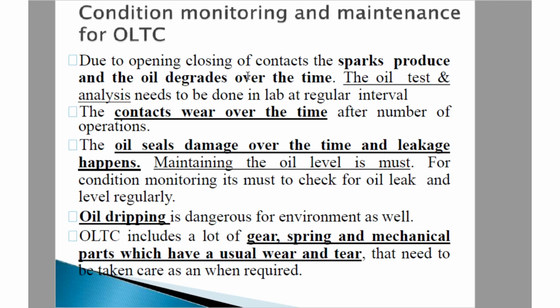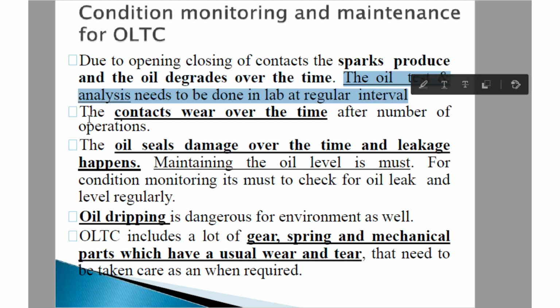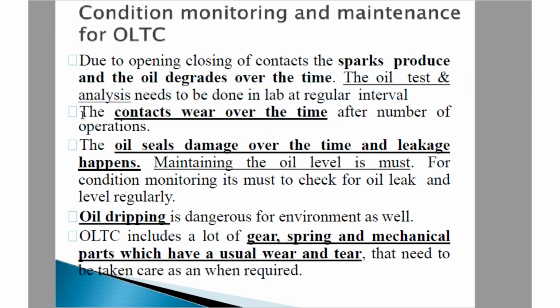We are interested in the condition monitoring and maintenance of OLTC. So this is the concept. Till now we have seen the concept of OLTC. Due to the opening and closing of the contacts, sparks are produced and the oil degrades over time. The oil test and analysis needs to be done in the lab at regular intervals. The contacts wear over time after a number of operations.